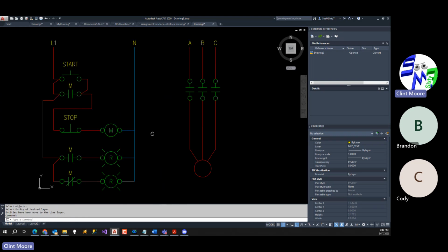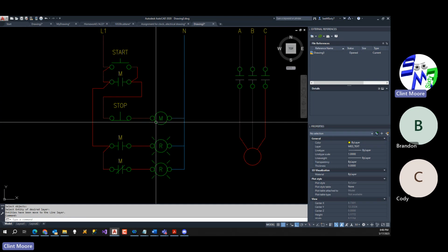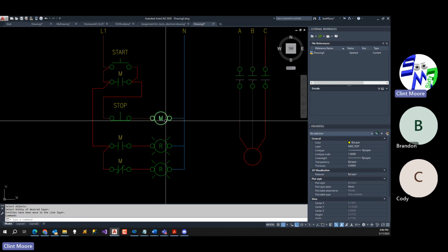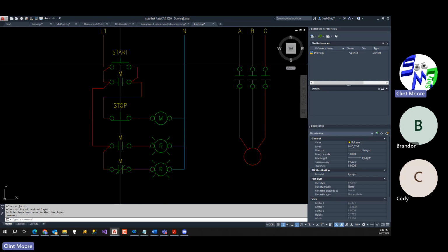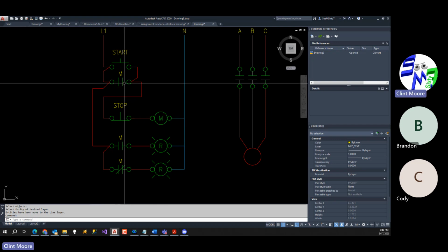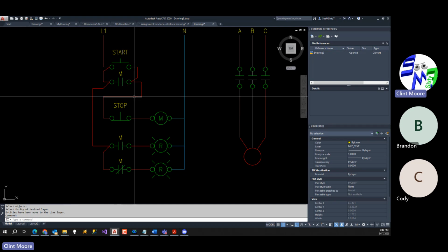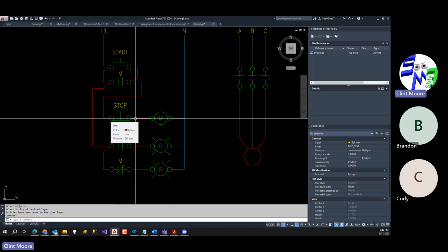All right. And then what will happen is when you hit the start button here, you momentarily push this button in. What that does is that engages the coil here. That coil becomes hot, it's energized, and it closes this contact here. So when you let go of this, it's still held in place by itself. This closes this contact and keeps it in place until it's disconnected. So now this circuit is flowing through here. It's coming right on through. Notice the stop switch is still there because it allows the electricity to flow right on through it.